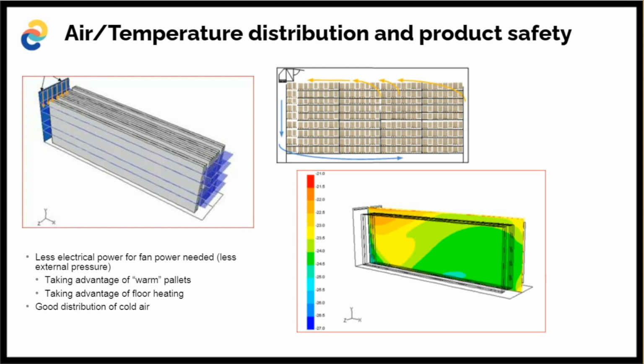We bring it down, and then we go up through the products. But it's very good to simulate that to determine what would be the frequency of the fans there, because we do not want to overdo it, and we want to make the fan speed as low as possible. And for that, we are using these CFD calculations to make sure to the customer that all the temperatures in this room are within the range.